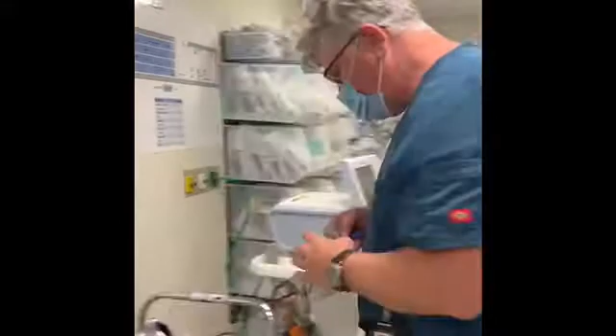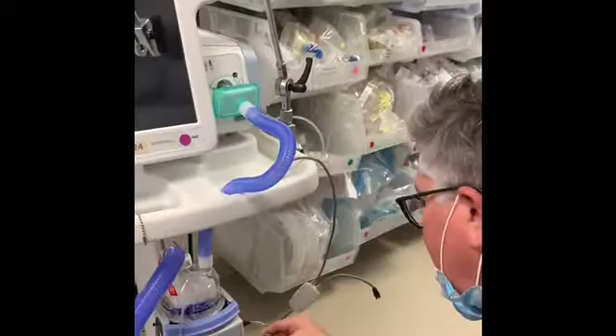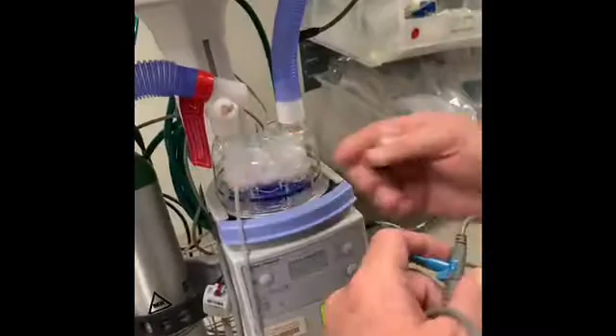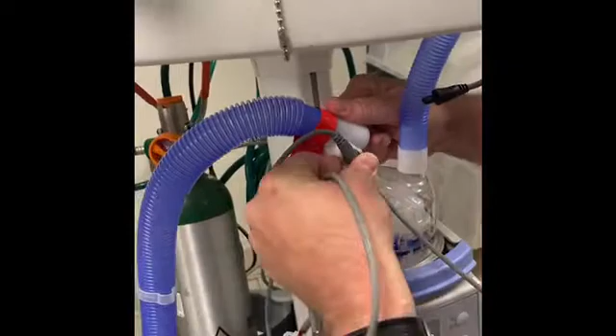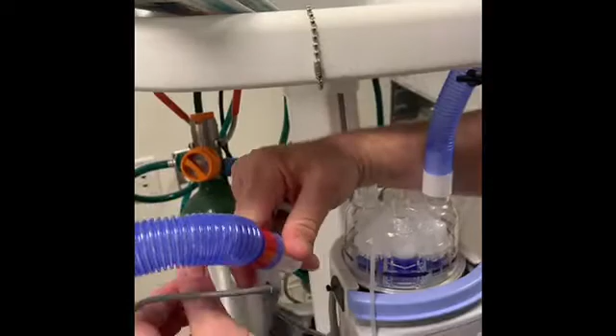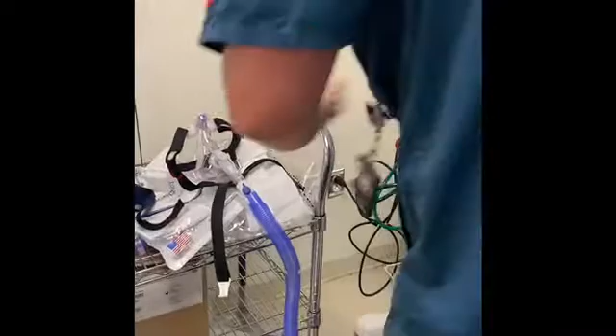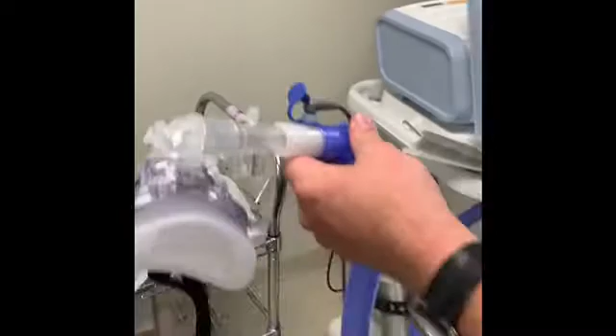The last part of the setup is the heated wire. We want to heat this, so we have our heated wire, which we use, same as on the ventilators. You have a port right here, which I just put, and it fits directly in, clips in place. You'll see it's like a little puzzle piece. It fits right in there. And what's that doing? It's measuring the temperature here, and then we measure the temperature at the distal end of the tubing, same as we do with the other pieces of equipment, and the other port goes here. So we're measuring the temperature in two spots, so it's a nice even temperature.